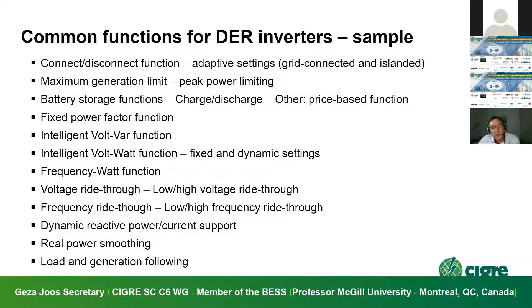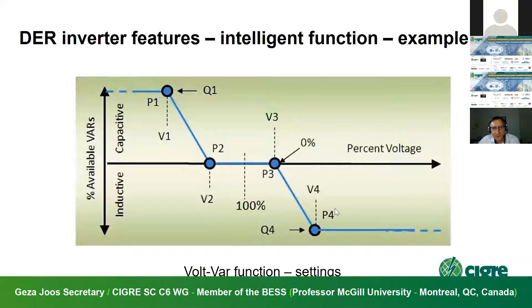An example of an intelligent function is one featured in the latest IEEE 1547 standard for DER interconnection. It's essentially a function that limits the voltage when you have overproduction and supports the voltage when it drops below the minimum value.